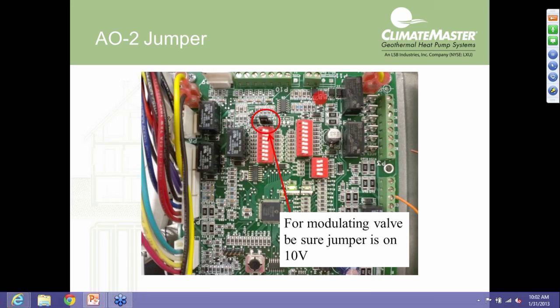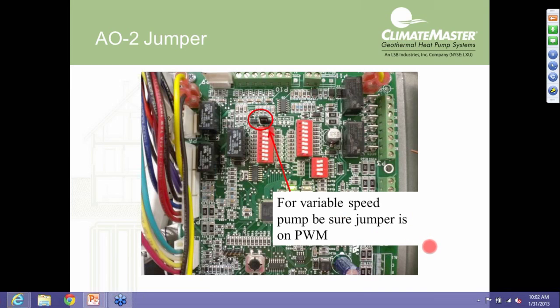And again, it should leave Climate Master in the right position for you for that model that it's built for. So for instance, there's 1 of 2 positions it can be in, and it's labeled right there on the board on the back side of it. Either the 10-volt position, and that's for the modulating valve, or the PWM position for the variable speed pump. PWM stands for pulse width modulation.